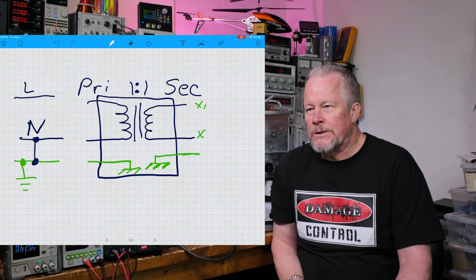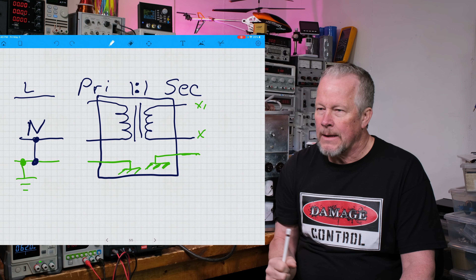You don't know which one is there unless you ohm it before you power it up. You don't want to ohm it when there's power on it, but you ohm it and you go, okay, this pin is tied to the chassis. Well, that pin, if it was tied to a line voltage, now that chassis is hot in reference to neutral, right? So now it's got two prongs, so you can plug it in either way. One way it's the housing's neutral, the other way the housing's hot. So that could be an issue, because you might think all your metals are all tied to the same thing, not realizing that the two prong doesn't know which way it's connected.